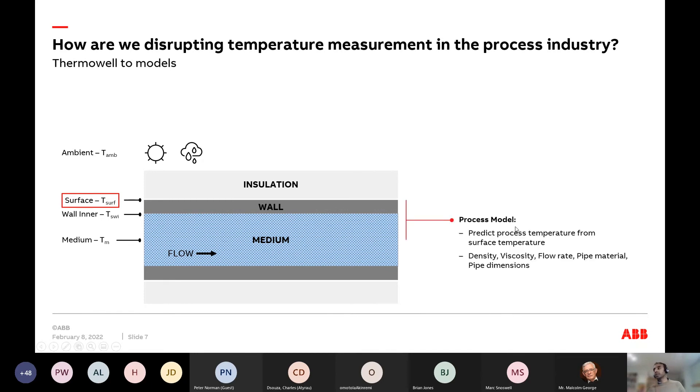We developed a process model — basically, given an accurate surface measurement, it allows us to predict the medium temperature of the process. It uses the exact same parameters you would use for calculating wake frequency for your thermowell: the same process parameters used in plant design or judging whether your thermowells will work. Taking density, viscosity, flow rate, pipe material, and pipe dimensions, we can predict the medium temperature from a given surface temperature.